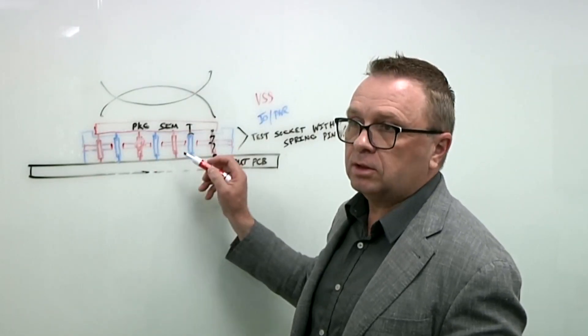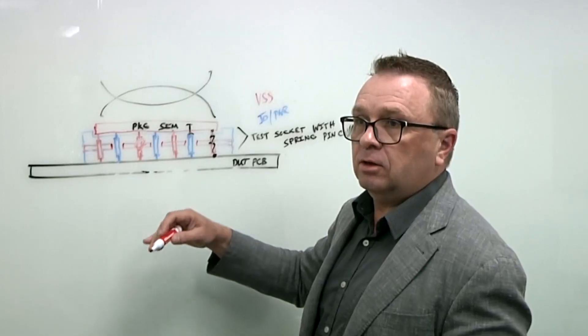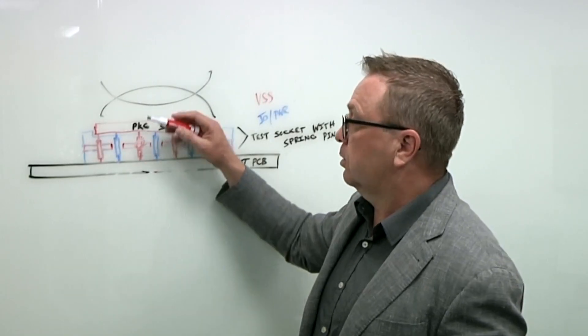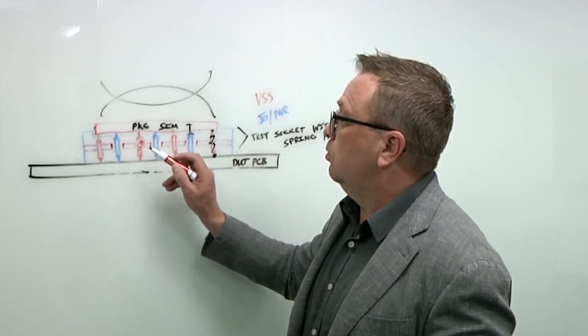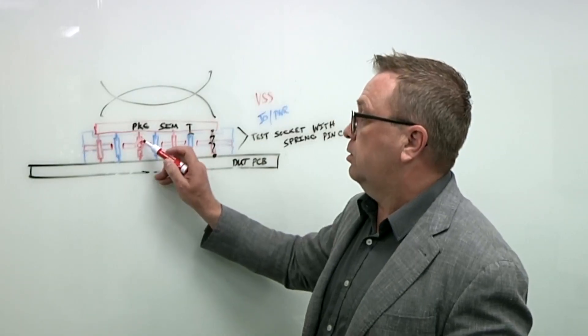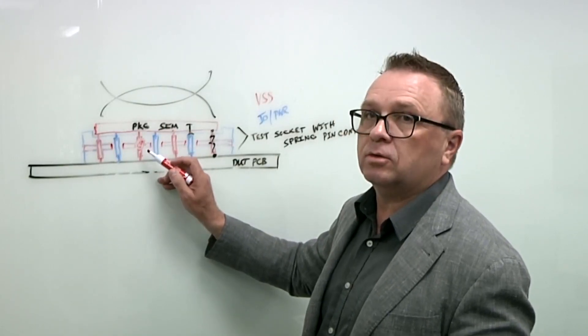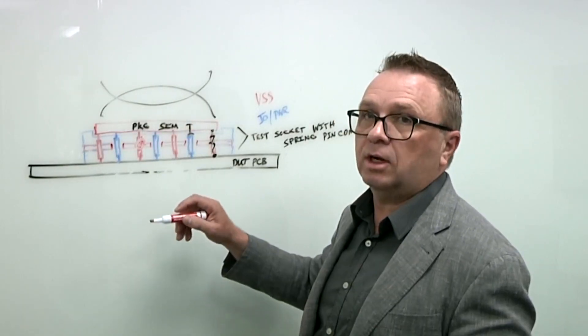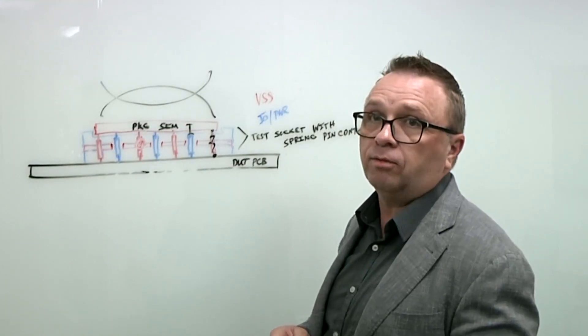So we have ways to do this offline outside of the test cell well before. So we characterize the sockets for how long this junction will last, the integrity of it, what the resistance will be over time, not to mention the contact resistance over time as well. So we do life cycle studies offline.